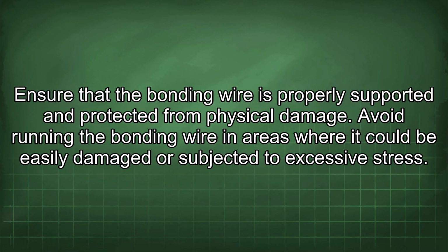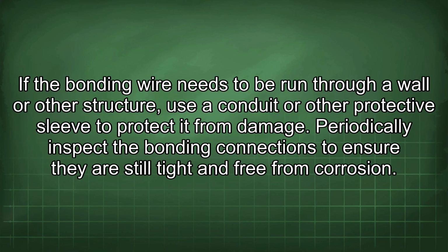Ensure that the bonding wire is properly supported and protected from physical damage. Avoid running the bonding wire in areas where it could be easily damaged or subjected to excessive stress. If the bonding wire needs to be run through a wall or other structure, use a conduit or other protective sleeve to protect it from damage.